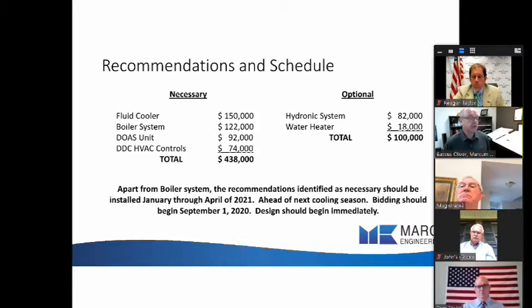Optional systems would be the hydronic improvements and the water heater, and they've got a total there that you see of 100,000. So apart from the boiler system, the recommendations identified should be installed January through April of next year. We need to be putting this in when the heating system's in operation and the cooling system is shut down. We need to do this ahead of the next cooling season because we may not make it through the next cooling season if we move the county clerk in and if we start having troubles with the fluid cooler.